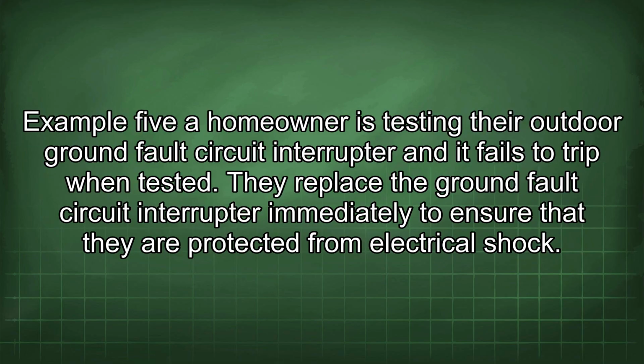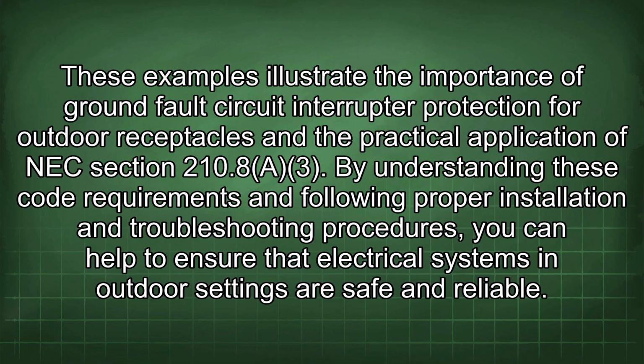Example 5. A homeowner is testing their outdoor ground fault circuit interrupter and it fails to trip when tested. They replace the ground fault circuit interrupter immediately to ensure that they are protected from electrical shock. These examples illustrate the importance of ground fault circuit interrupter protection for outdoor receptacles and the practical application of NEC Section 210.8A3. By understanding these code requirements and following proper installation and troubleshooting procedures, you can help to ensure that electrical systems in outdoor settings are safe and reliable.